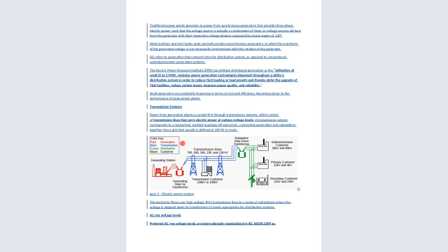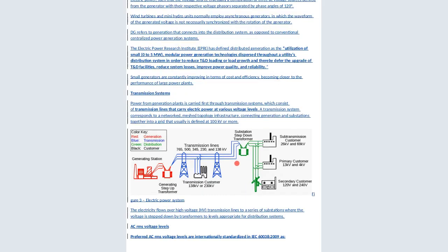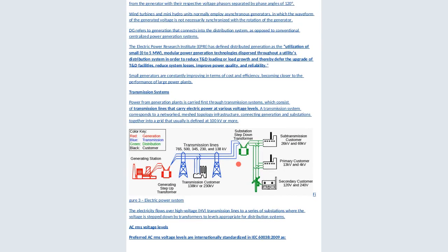Now the transmission system: the power from the generation plants is carried first through the transmission system, which consists of the transmission lines that carry electric power at different voltage levels. So the transmission system corresponds to a meshed network topology infrastructure connecting generation and substations together with a grid that usually is defined at 100 kilovolts or more. When we look at this diagram down here, it is a transmission system. The color codes are given so that it can show where we are at which step. The red is the generation. At this point, power is generated.